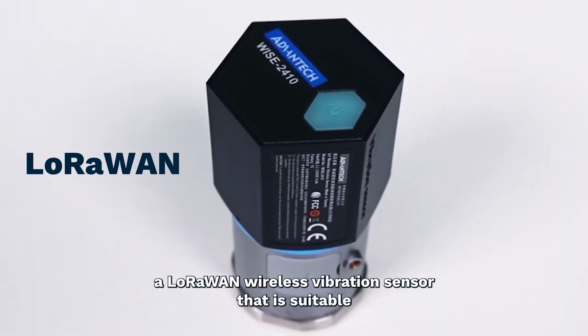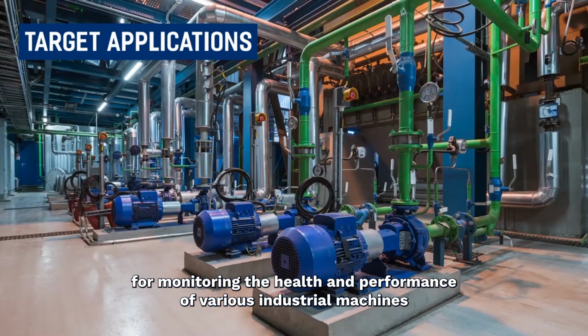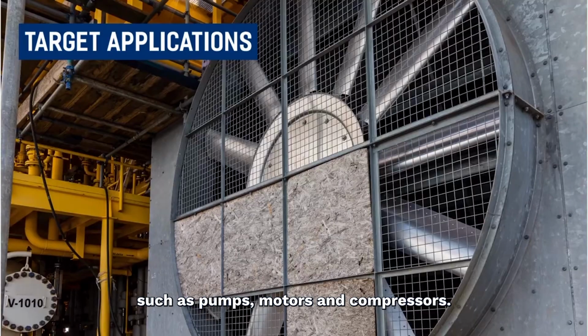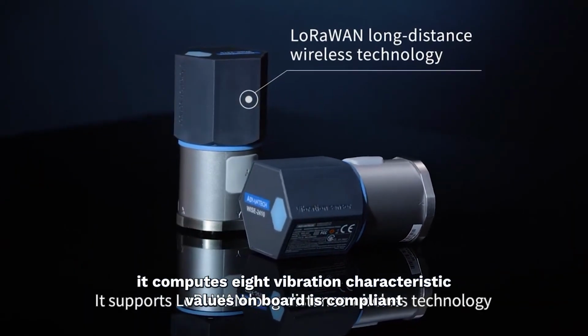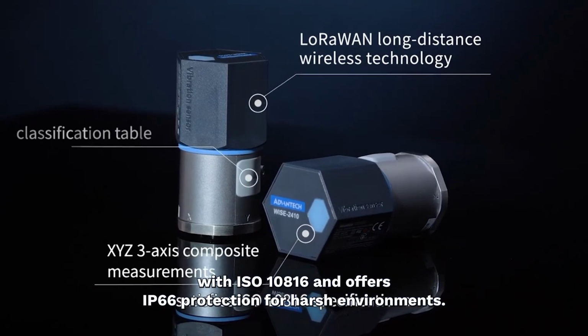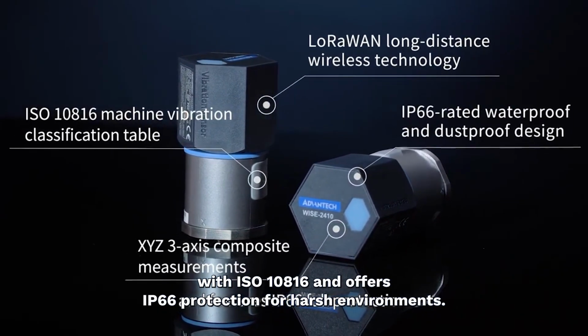The Wise-2410 is a LoRaWAN wireless vibration sensor that is suitable for monitoring the health and performance of various industrial machines, such as pumps, motors, and compressors. Featuring a built-in 3-axis accelerometer, it computes 8 vibration characteristic values on board, is compliant with ISO 10816, and offers IP66 protection for harsh environments.